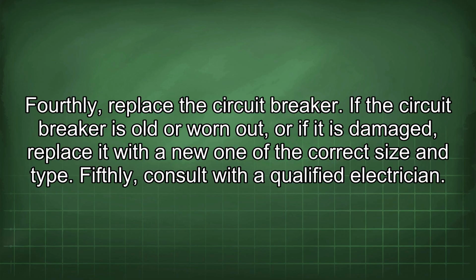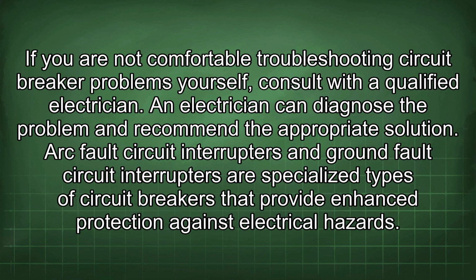Fourthly, replace the circuit breaker. If the circuit breaker is old or worn out, or if it is damaged, replace it with a new one of the correct size and type. Fifthly, consult with a qualified electrician. If you are not comfortable troubleshooting circuit breaker problems yourself, consult with a qualified electrician. An electrician can diagnose the problem and recommend the appropriate solution.